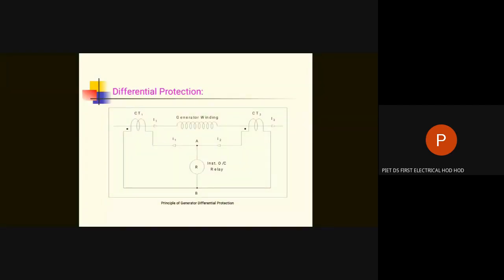For such faults, and we shall see if time permits, for line to ground fault a very different kind of protective system is used, because the line to ground fault is passing through the stator laminations, and if a large current passes, say for a 15.75 kV generator, if we don't restrict the value of the current, then the current can be in terms of thousands of ampere, some 15,000 or 17,000 ampere or even more. In that case, the generator stator laminations would get sintered. They would be connected together. Sintering means they are welded together. Welding would happen, and it would need quite a long time to repair such a stator. Therefore, the stator current due to a stator earth fault is reduced to a very small value so that it cannot damage.